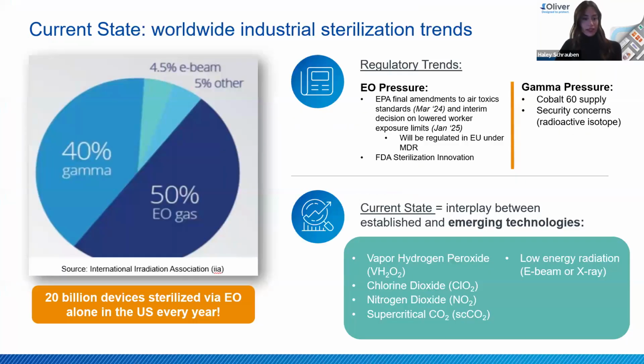But before we dive into chlorine dioxide specifically, we thought it would be a good idea to ground the audience in what is happening in industry. So today, almost all single-use sterile devices are sterilized via ethylene oxide or gamma radiation. In the US alone, about 20 billion devices are sterilized by ethylene oxide annually. But due to regulatory and supply chain pressures, there's incentive for organizations to explore alternatives and diversify those options. To be clear, ethylene oxide and gamma aren't going anywhere. They've got broad compatibility, excellent penetration, and they're positioned to handle high volumes. So what this actually looks like today is more of an interplay between established and then emerging technologies.